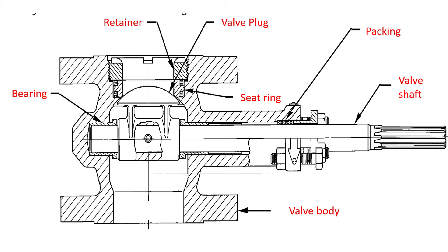You can see that the components available in the sliding stem control valve are also included in the rotary shaft valve, though there are some different components. The valve body is the fluid boundary and the pressure-containing component — this is where the process fluid, which has pressure, temperature, and chemical properties, enters. This is called the trim, which refers to the process fluid interacting with the internal components of the control valve body.